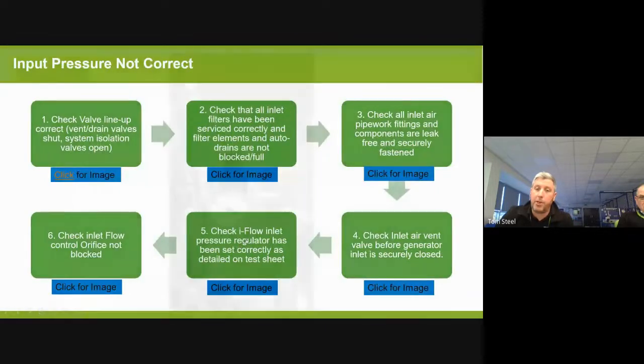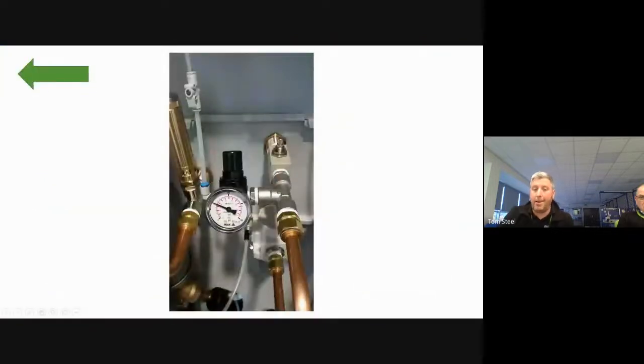We need to ensure these valves are in the correct position for the generator to work correctly. We're going to check the pressure regulator as well. So internal to the generator, we have an output pressure regulator and we have an output flow controller. These are things you don't want to adjust. What you'll find is the system will be preset in the factory, and during installation, it has to be checked to ensure the flow is correct.